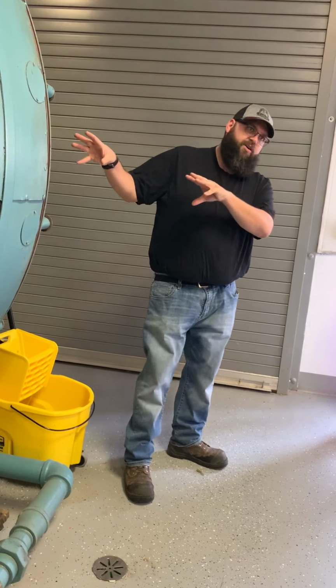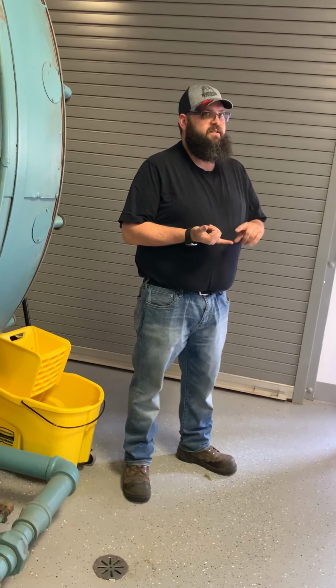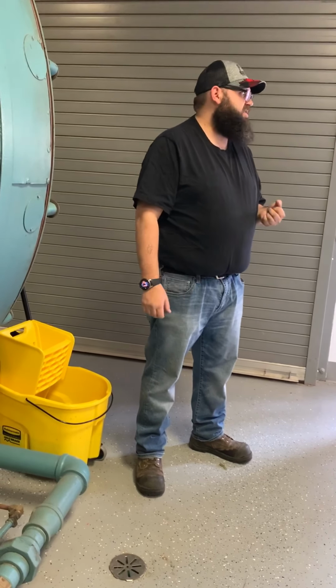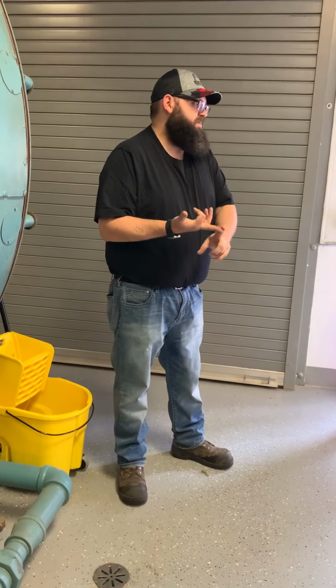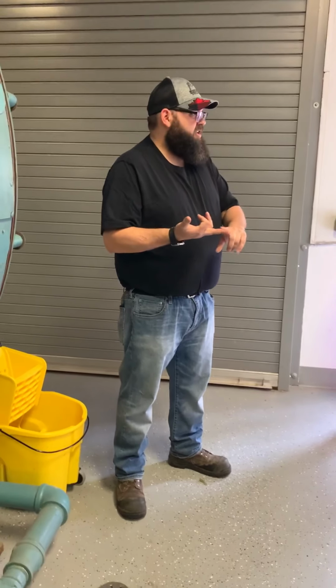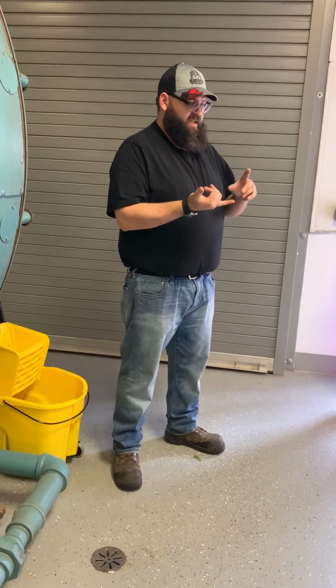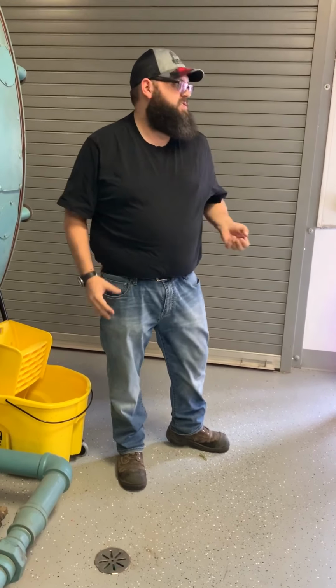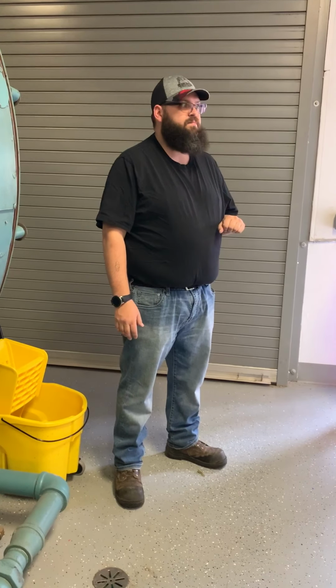We do a little bit of water treatment, and the only thing we really do is put it through a water softener, and that takes out a lot of that scaling. Hard water is basically what causes that. The softener takes the calcium and the magnesium out of the water and replaces it with sodium. Sodium is soluble in water, it'll carry through in steam, and it's basically salt. Whereas the calcium and the magnesium produce that hard scale, which can affect the boiler's efficiency, and after a long period of time can really do some damage to it.